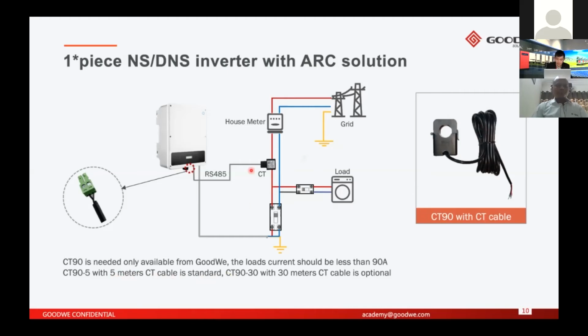If you think 5 meters is not enough, you can also order CT90 and 30. The 30 means the CT cable will be 30 meters. So you can order the CT from GoodWe together with the CT cable, and the CT cable can be 5 meters or 30 meters.